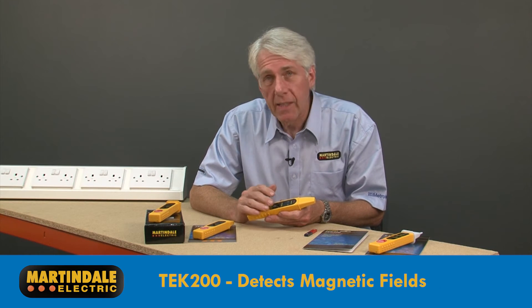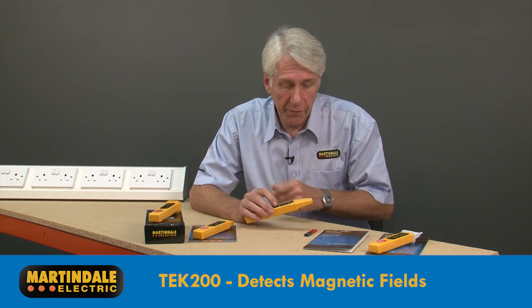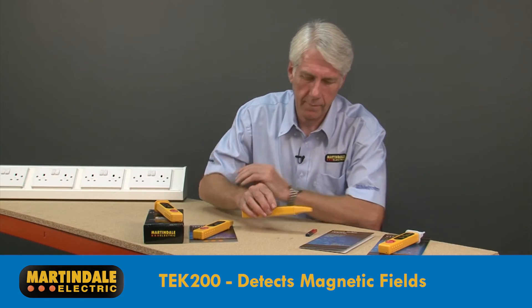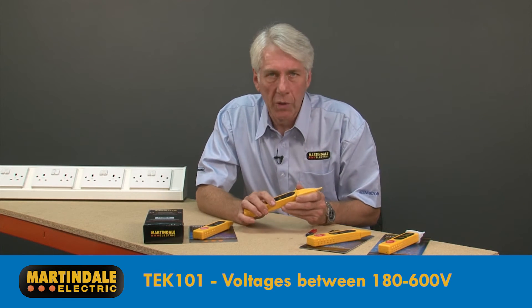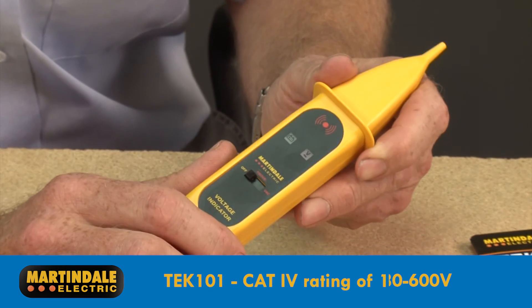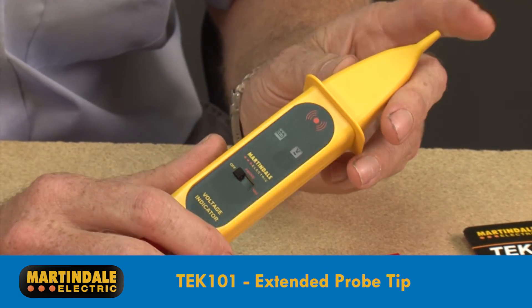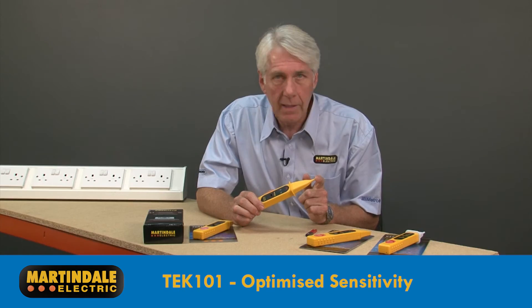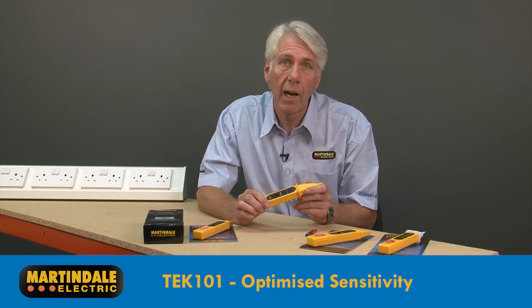The TEK200 has the additional capability to detect the presence and polarity of magnetic fields produced by relays, solenoids and transformers. The TEK101 will detect the presence of voltages between 180 and 600 volts but has a CAT4 rating of 1000 volts. This product has an extended probe tip for accessing conductors in confined spaces, and its sensitivity has been optimized for discriminating between adjacent conductors at close range.